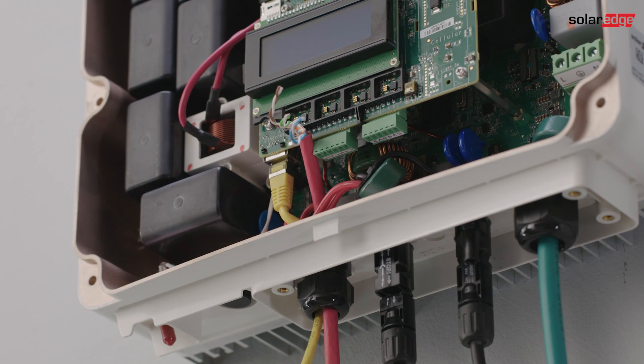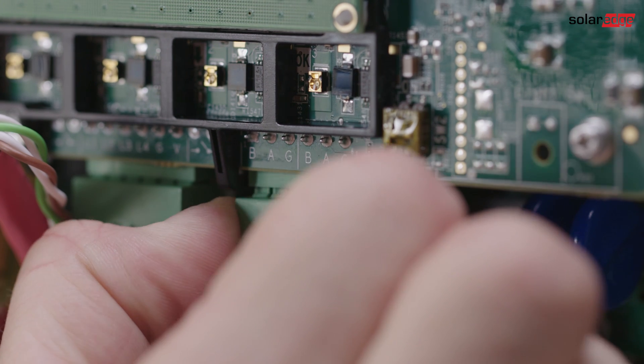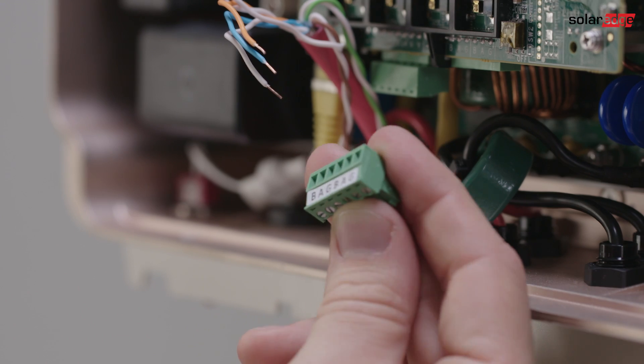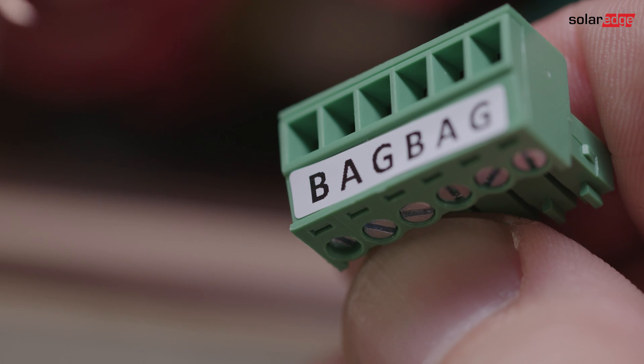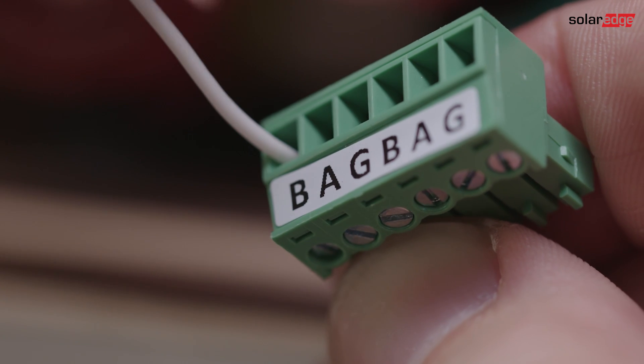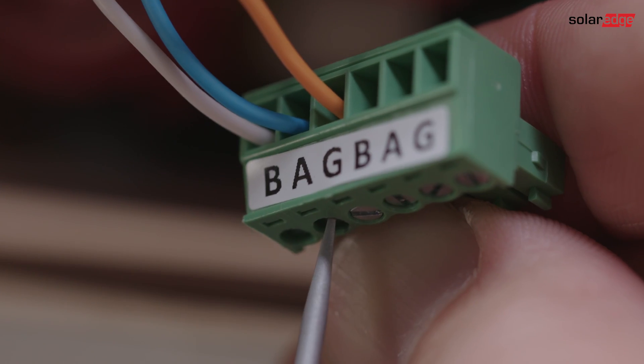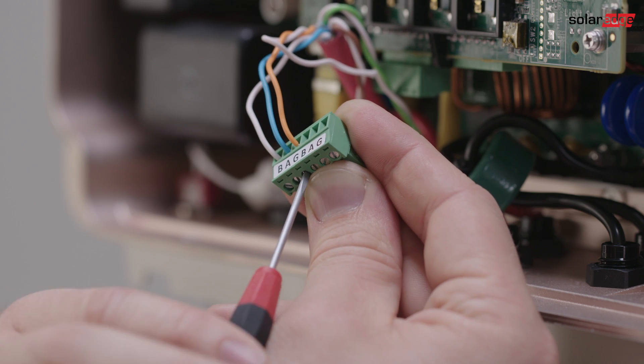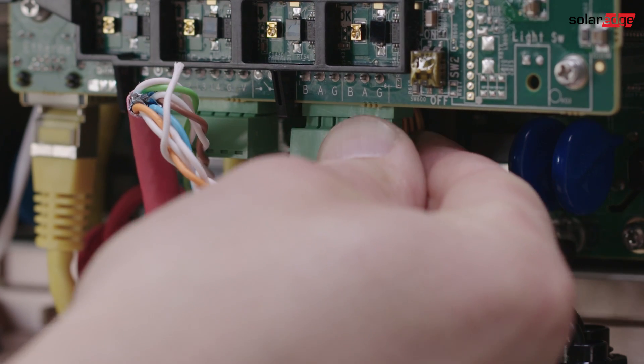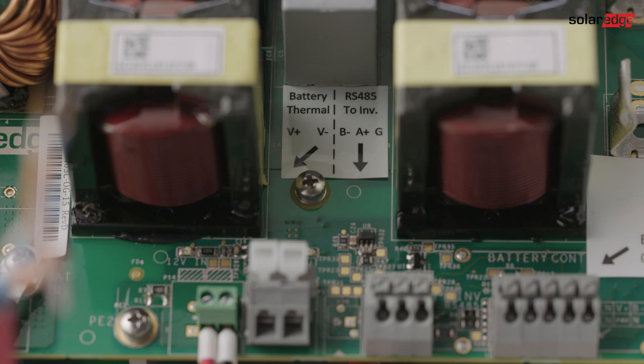In the next step, connect the communication between the inverter and interface. For this, we need a shielded twisted pair cable; we recommend using a CAT5 cable. When connecting RS485, a twisted pair must be used for the B and A terminals between inverter and interface. We recommend using white and blue. For the G terminal, any other wire can be used; we recommend using orange. Screw terminals are used for the RS485 connection on the interface.